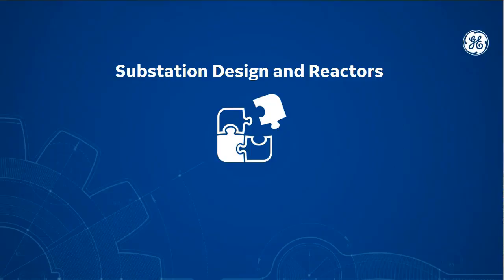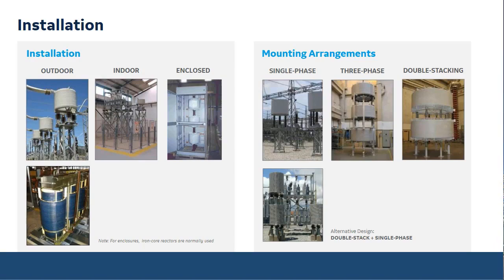So, talking about substation design. Adding a reactor to the system means that you're going to add an impedance, and when there's current flowing through the impedance, it creates losses. The reactor is an inductance, so it's a reactance that is added to the system. So we also need to think about the TRV issues that an inductance may cause by being added to the system. Impedance also causes voltage drop; current flowing through the reactor causes the voltage drop.